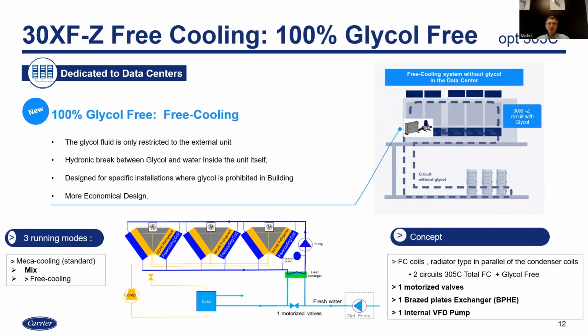So this is an option in which the customer wants to use water in the main loop, and in this case we are adding an additional heat exchanger with a small pump, and then we have glycol only in the hydronic free cooling section of the unit. And the main flow is water coming from the customer. And basically, if we have free cooling operation, we close this valve, water goes through this heat exchanger and then through the evaporators, and this heat exchanger provides free cooling by application of the pump here in free cooling operation. So it basically makes the system independent in terms of fluid between what is in the main circuit and the hydronic free cooling circuit. However, you have an additional heat exchanger, which makes it a little bit less efficient.